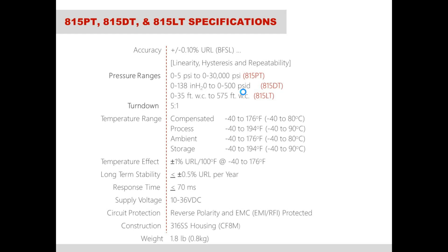You'll notice that this is actually larger than the 805 PT, and the reason for that is because we're adding HART communication protocols and a microprocessor and other components that basically the electrical signal has to be filtered through, but it increases the response time for the transmitter. Now, 70 milliseconds is still really good for a HART device.